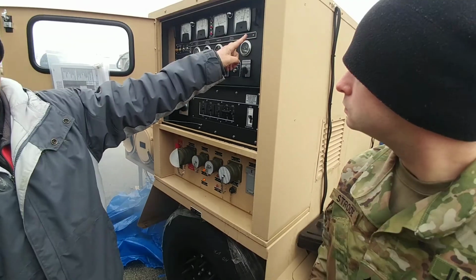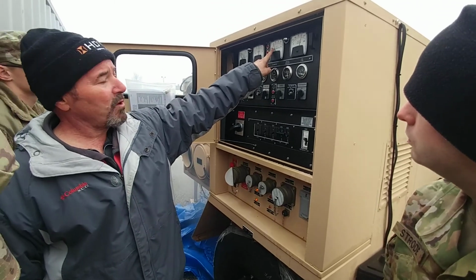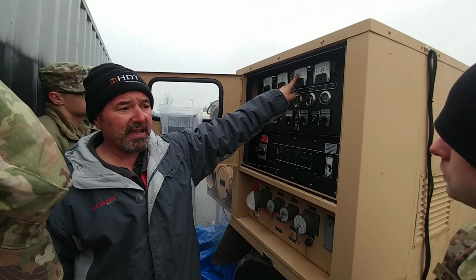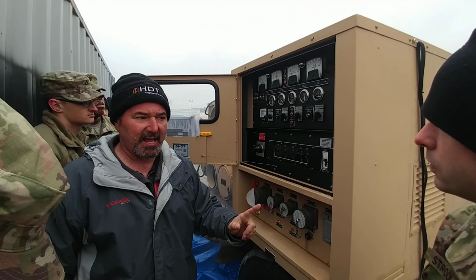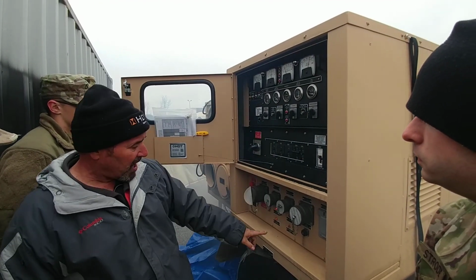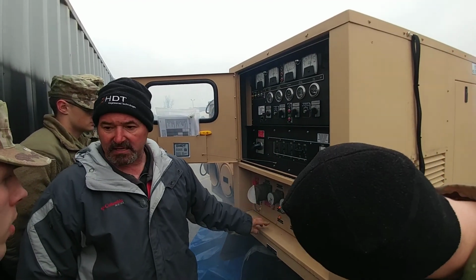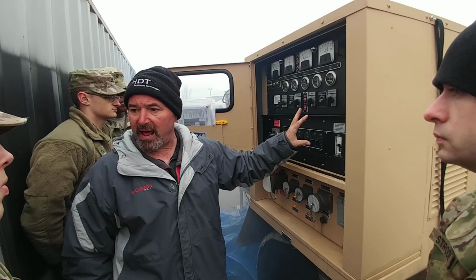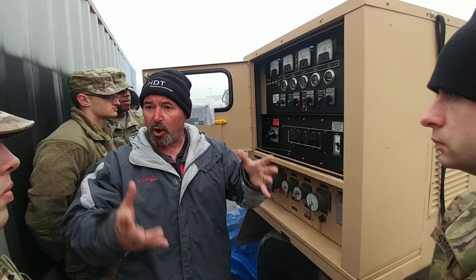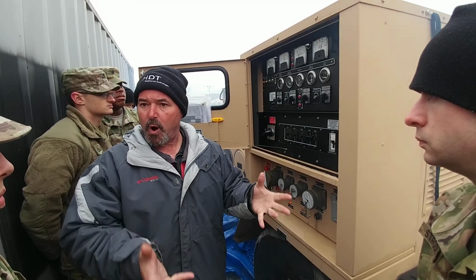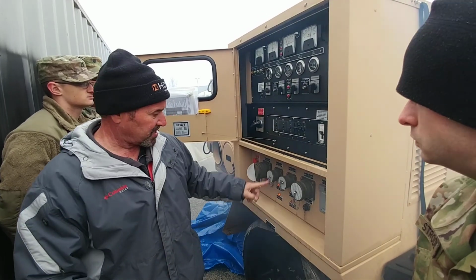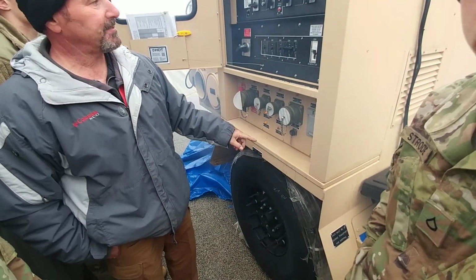Your gauges come on. Right now we're running at around 10 to 12 kW because it's got a dummy load on it - you got your 6 and your 4K load bank. So it's got a load on it already, so it won't ever gum up on you. It's called a wet stack. It won't wet stack on you because you got a 6 and a 4K load bank.